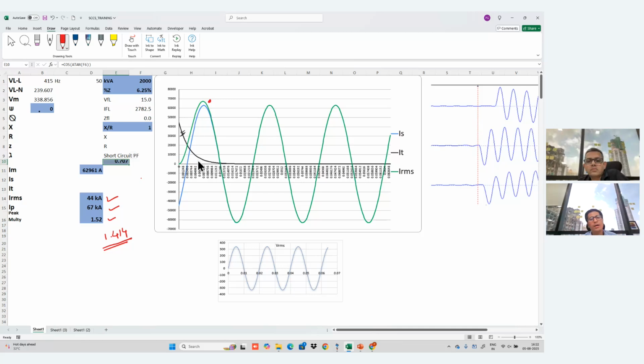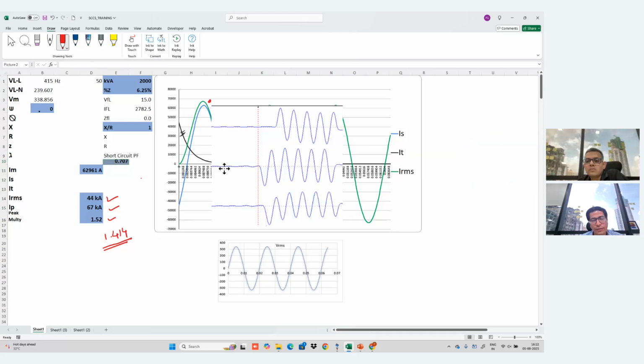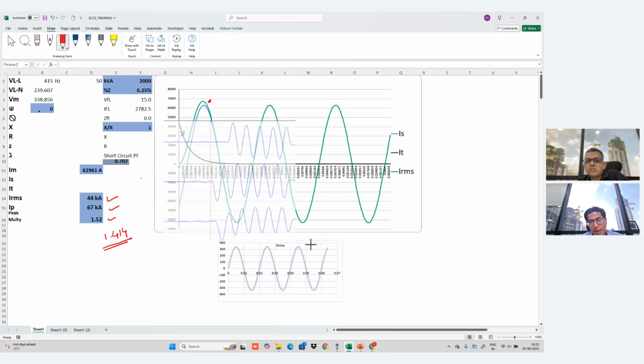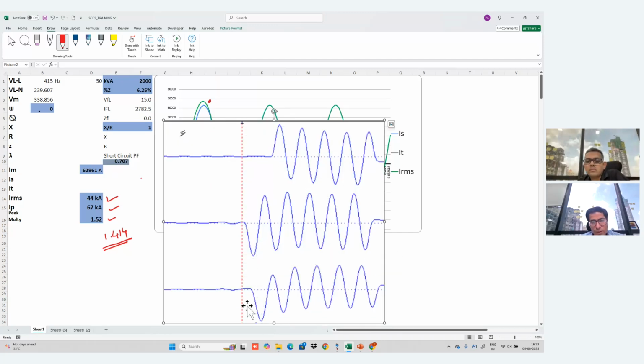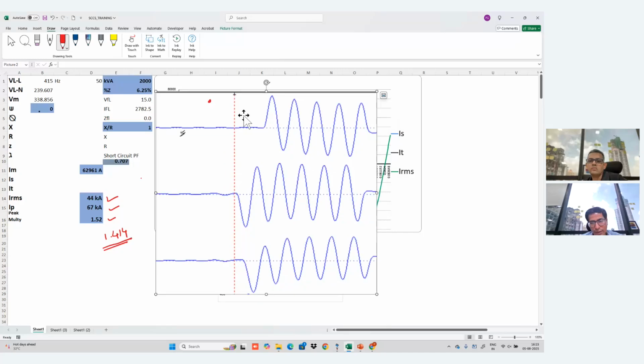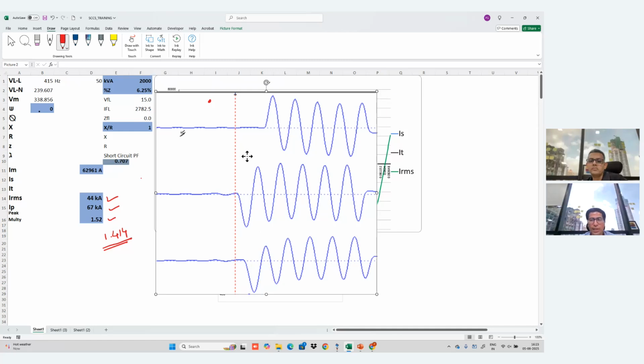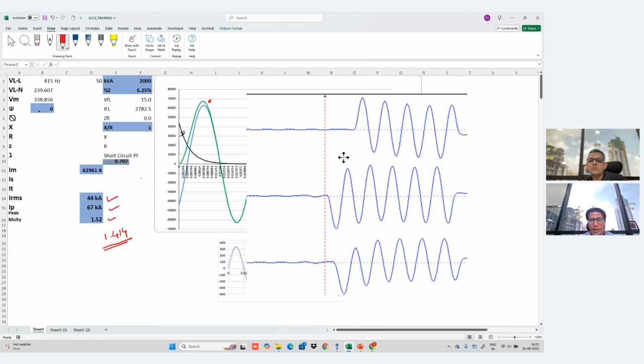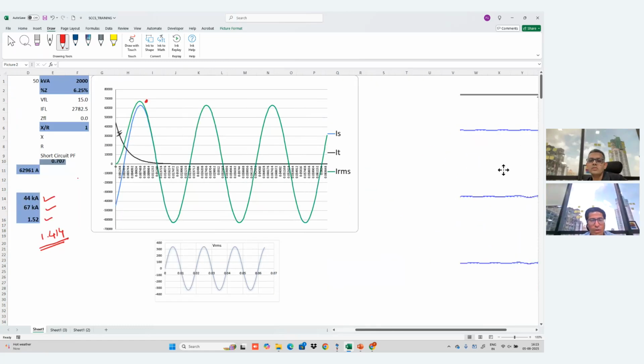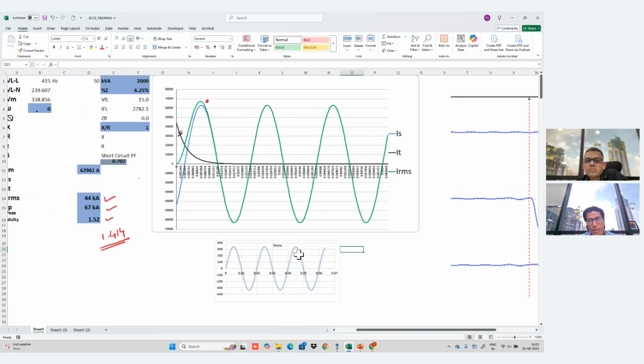Now we'll see one particular disturbance record that is actually a real-time short circuit taken from the relay. You can see the asymmetry here. This was at one of our clients, where this event occurred and a short circuit was recorded, and this is the waveform taken from the relay. You can clearly see the DC component is there. The asymmetry is really clearly visible here. So in actual conditions we also get this kind of waveform. This is not only limited to calculations, but in reality we have this kind of waveform in the field.